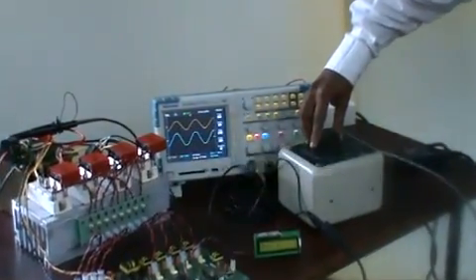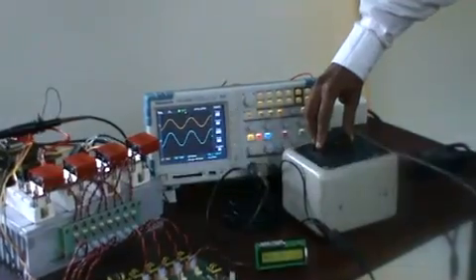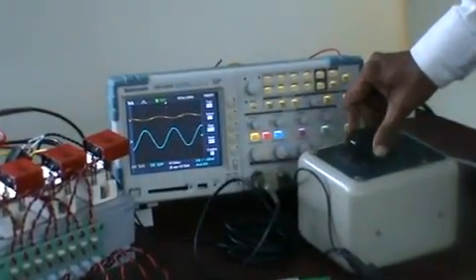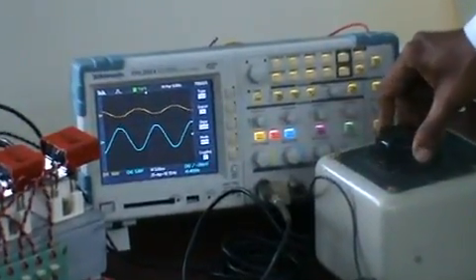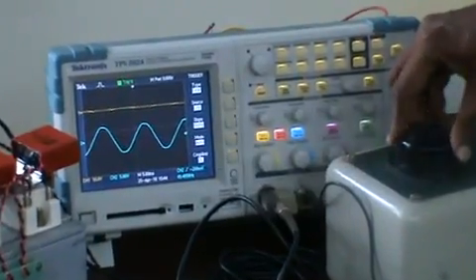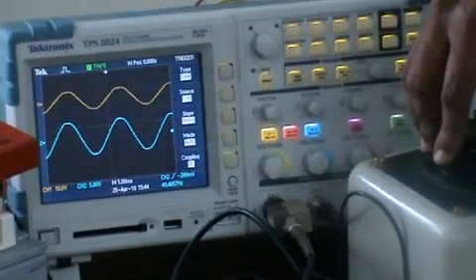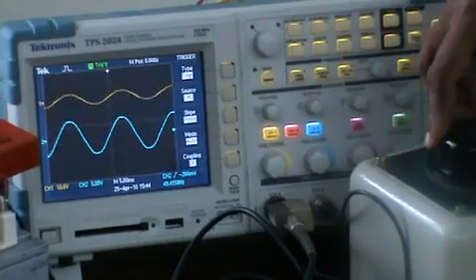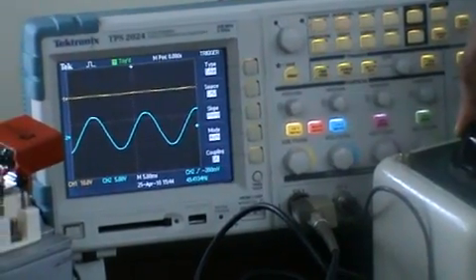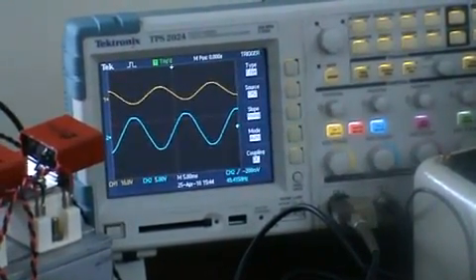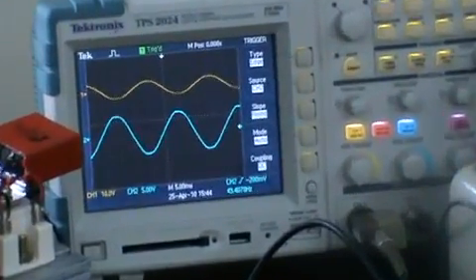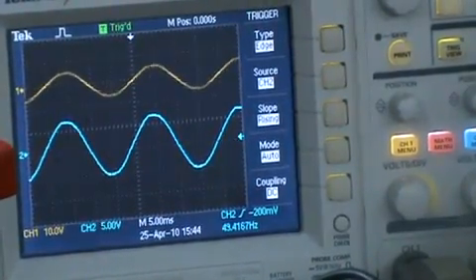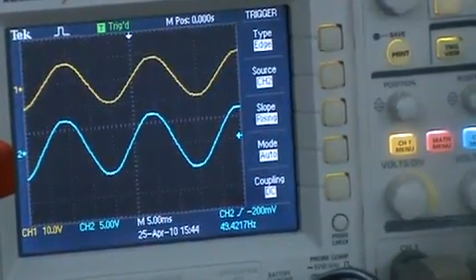Now the yellow trace is the correction voltage generated by PWM using the IGBT, and blue is the output voltage. When I reduce the voltage you can see the yellow comes in-phase with the input. When I increase the voltage, the yellow shifts to the opposite phase. This voltage adds or subtracts with the mains so the output remains constant.